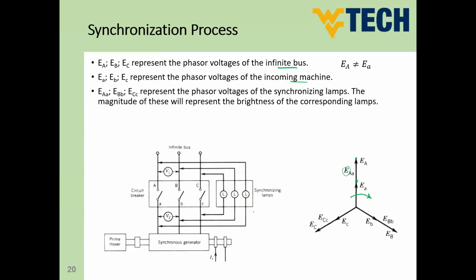So we can detect that using synchronizing lamps, as you can see here in this figure. This operation, guys, is not very easy, and there is a device called the synchronizer doing that control on two systems. One is called the speed governor, and one is called the automatic voltage regulator. These two systems are controlled by the synchronizer in order to provide the synchronization conditions to connect the generator to the infinite bus. Okay, nice.